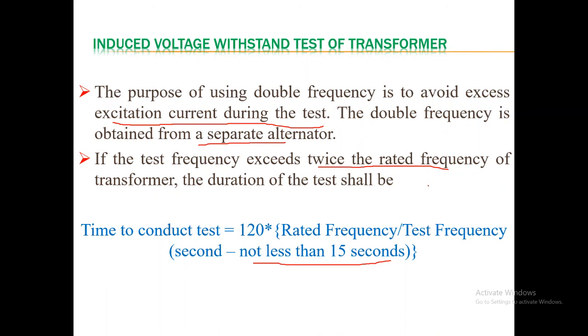But when you are calculating it, at least you have to take care of this. The time for which you apply the voltage with that non-standard frequency value should not be less than 15 seconds. So this is about the induced voltage withstand test on the transformer. Thank you.